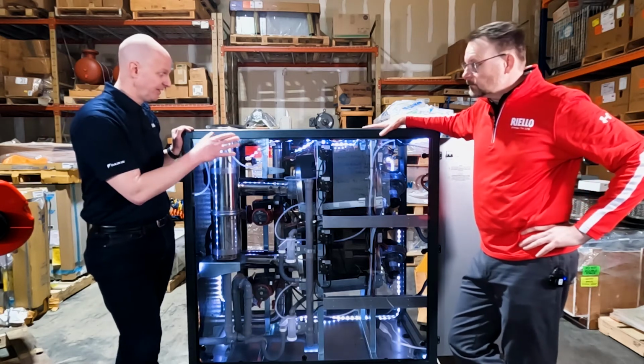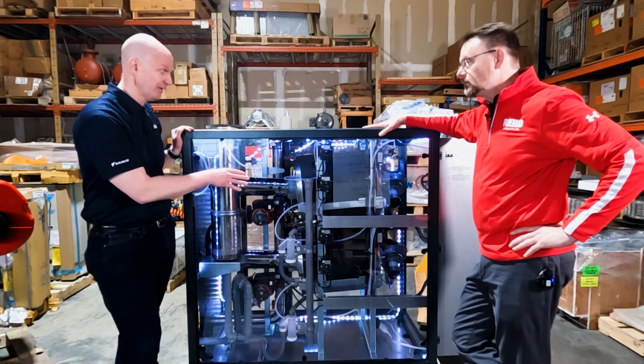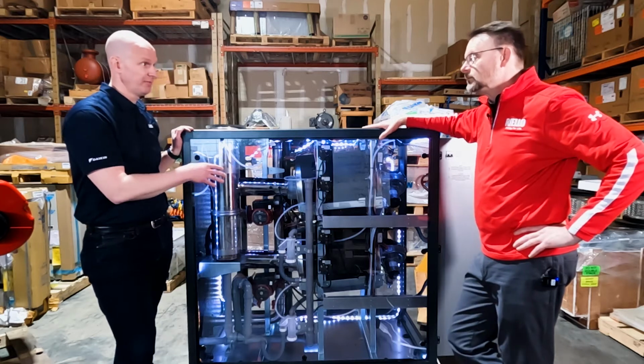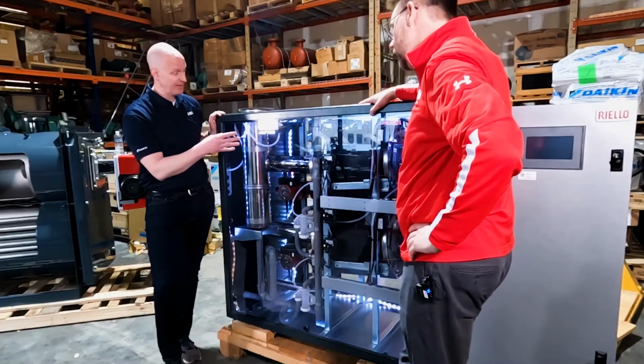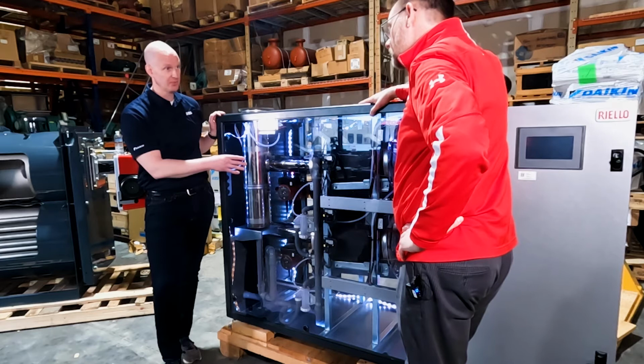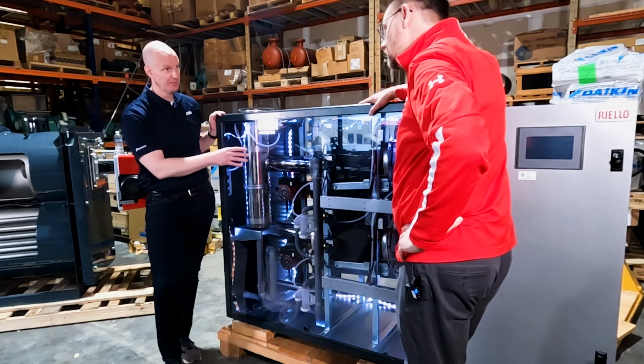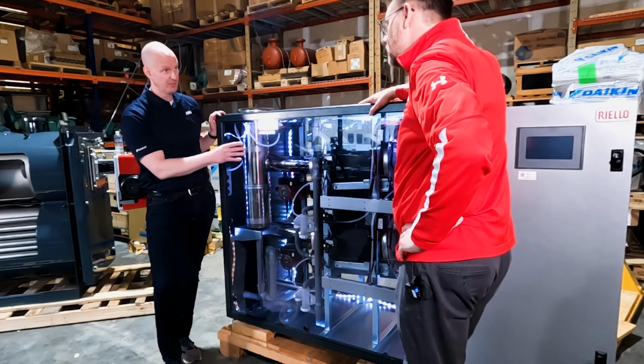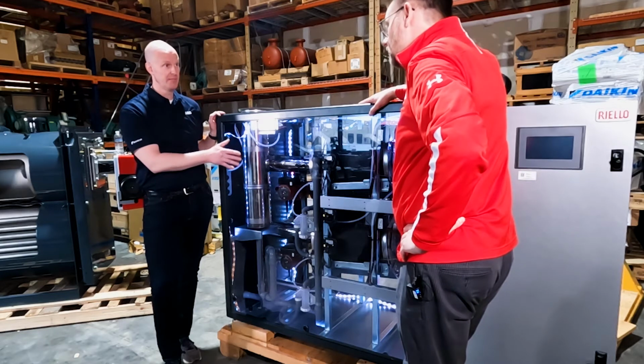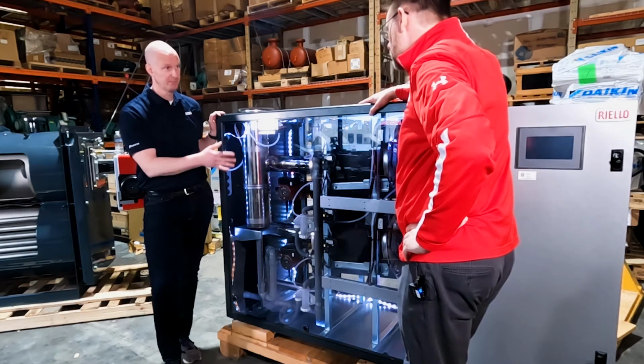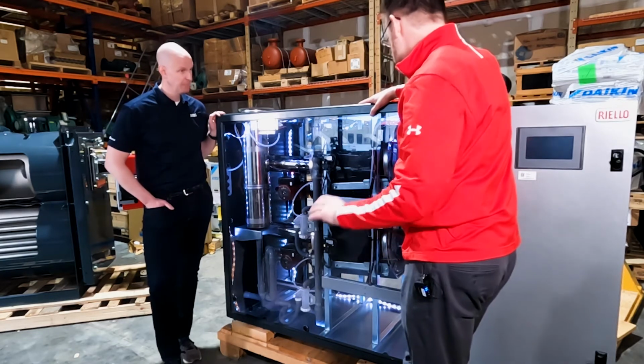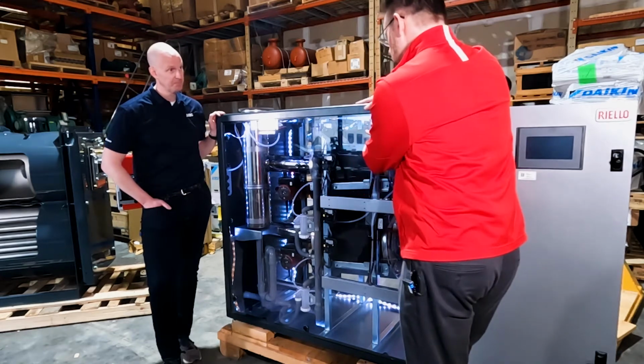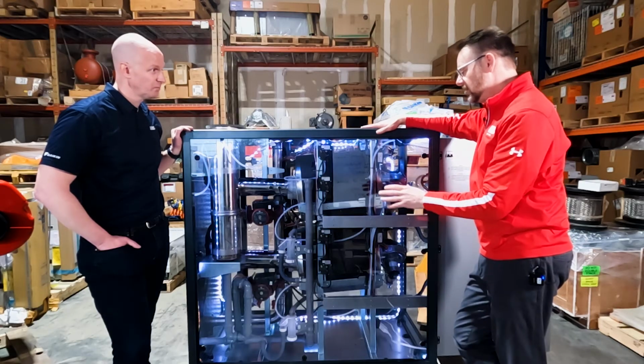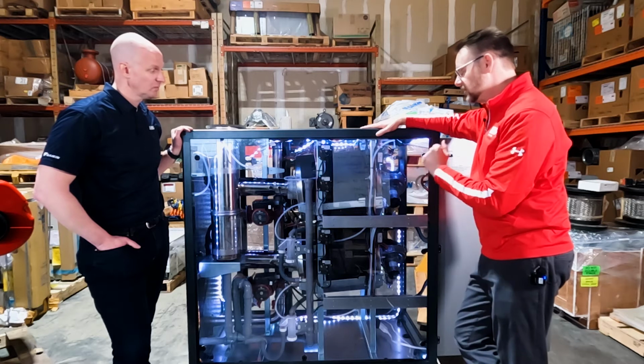We have redundancy in the cabinet. It gives us a lot more flexibility from a turndown standpoint, and we can actually isolate not only the combustion but the flow. We can service a heat engine independently while the others are running. So the turndown of the cabinet is actually the combined turndown of each of the connected heat engines.